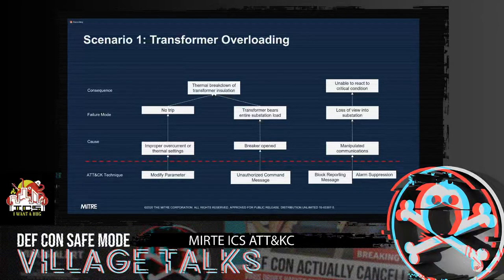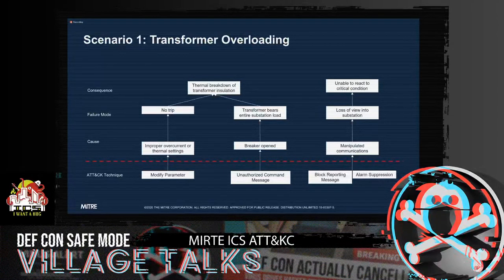We can structure this failure scenario to understand exactly what we're trying to accomplish. Taking scenario one — transformer overloading — the consequence is thermal breakdown of transformer insulation. We have a couple of failure modes: we don't want the protective relay to trip, so we put in improper overcurrent and thermal settings. We also want one transformer to bear all the load, so we open the breakers to the other transformers. We do this using the attack technique of modifying parameters and sending an unauthorized command message. Now we have a full story of how we're going to cause this thermal breakdown.